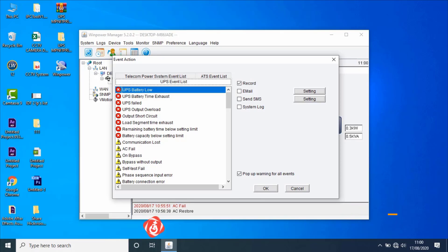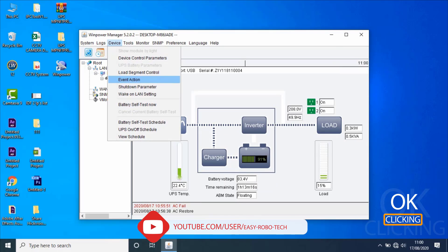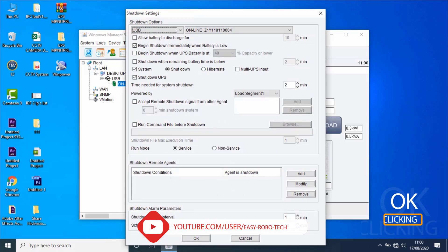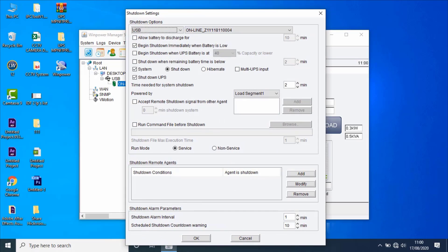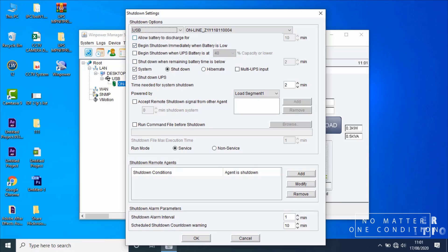Make the configurations, then click OK. Go to the next option — Shutdown Parameters. It's a UPS shutdown control settings. When the UPS is abnormal, software will shut down UPS output. There are five conditions; no matter which one condition is met, software will send a shutdown command to the UPS.